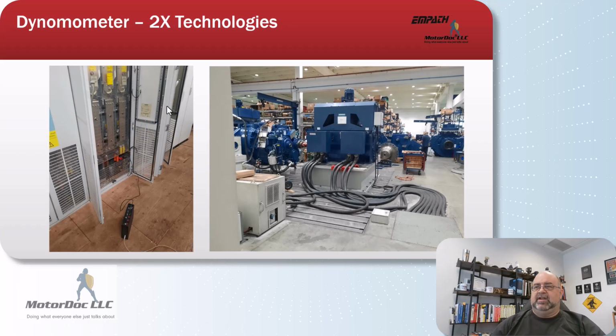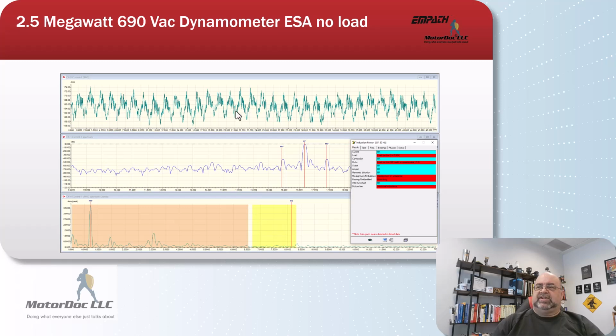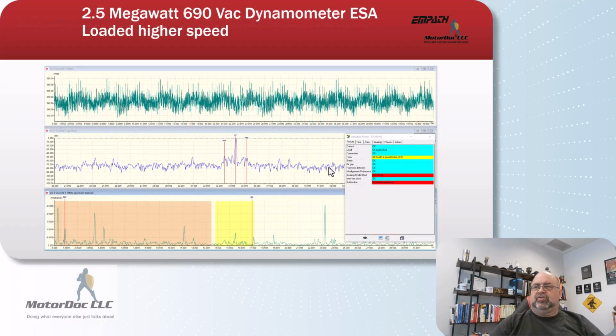There's a continued study. This is a dynamometer machine. This one here is 2.5 megawatts, 690 volts. This is possibly a fractured rotor bar. So we take a look at this and see the pole pass frequencies there, which are relatively high, but it really didn't affect the operation of the dynamometer too much, so they had continued using it. Other things here have to do with the gearboxes that are on that. As we take a look at it, we're seeing the entire system. So these are bearings and gears, and then there's more frequencies further on.